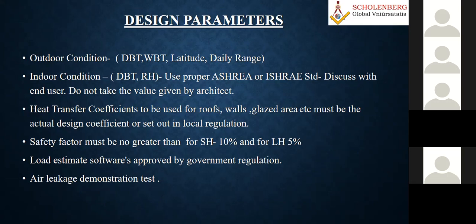I have also told my case study when we were doing a clean room in the Hindustan Cables Limited many years ago. The consultant or the people wanted to have 18 degrees centigrade inside, which I felt was a waste of energy. Later, when I discussed with the process consultant, they agreed they needed only about 26, 27, 28 is also okay. Just imagine from 18 to 26, where the 18 degrees was required only on some amount, 10% or 20%, of the total area. The area may be 50,000 square meters or something like that. So these types of things you can always interact on.